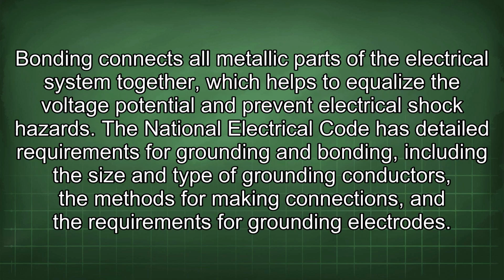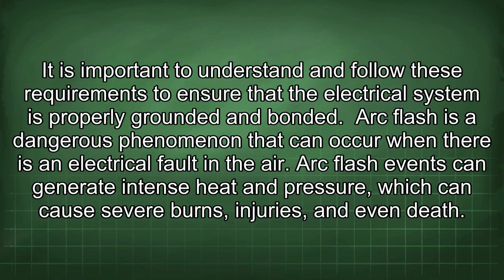Bonding connects all metallic parts of the electrical system together, which helps to equalize the voltage potential and prevent electrical shock hazards. The National Electrical Code has detailed requirements for grounding and bonding, including the size and type of grounding conductors, the methods for making connections, and the requirements for grounding electrodes. It is important to understand and follow these requirements to ensure that the electrical system is properly grounded and bonded.